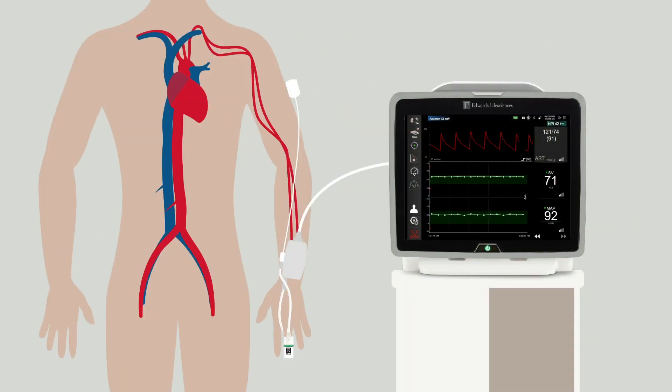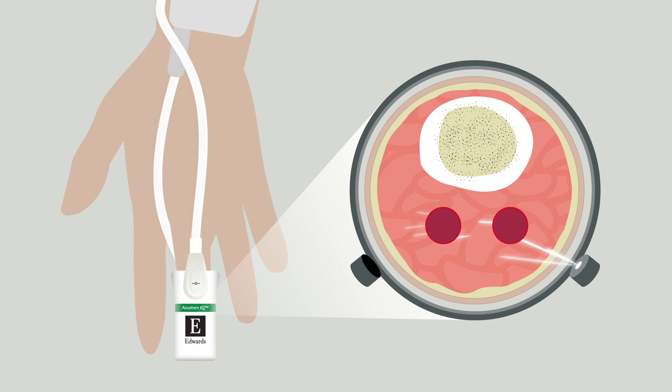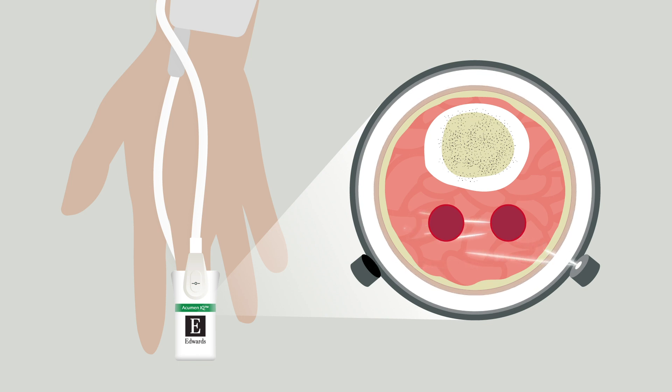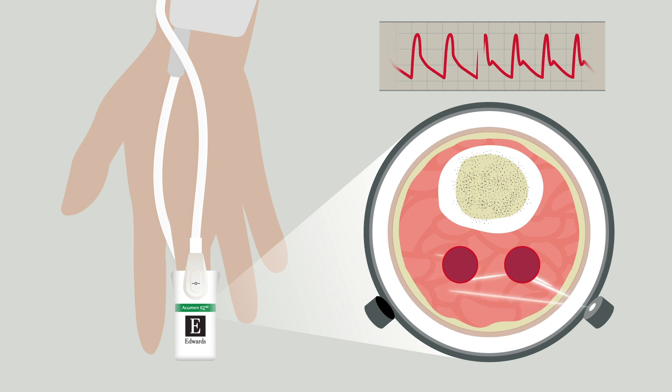Now let's take a moment to talk about how this technology works. All of Edwards' non-invasive finger cuffs combine the volume clamp and physio-cal methods to measure continuous and accurate beat-to-beat blood pressure. The essence of the volume clamp method is to dynamically provide equal pressures on either side of the wall of the finger arteries by clamping the artery to a certain constant volume. The pressure in the cuff is then adjusted a thousand times each second to maintain a constant diameter of the arteries. Continuous recording of the cuff pressure results in a real-time pressure waveform, which is then reconstructed from a finger pressure waveform into a radial arterial waveform.